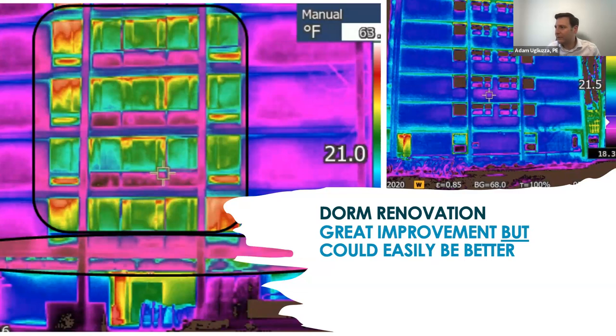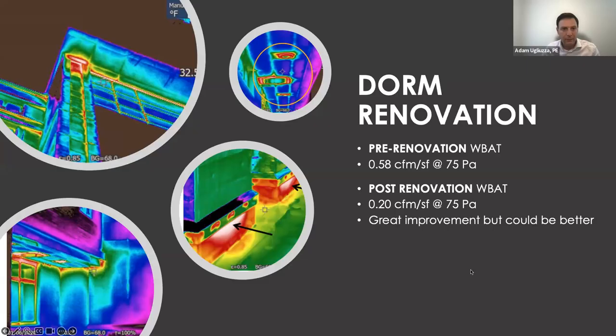This was a building renovation. On the left was the pretest, and the right image was the post-test. They replaced all the windows, did some sealing of the facade, and had a tremendous amount of improvement. But I still found leakage points at canopy conditions, soffit penetration conditions, and again, the mechanical curbs. They did really well, but we came in at 0.2, and we still had significant leakage sites. So again, just because you pass this test doesn't necessarily mean you have everything sealed up.